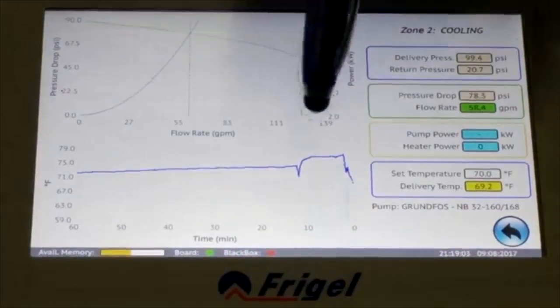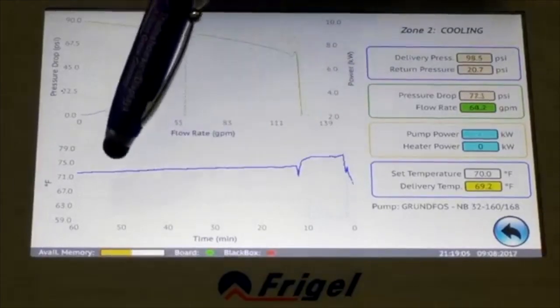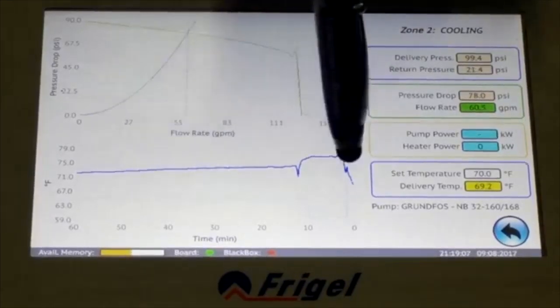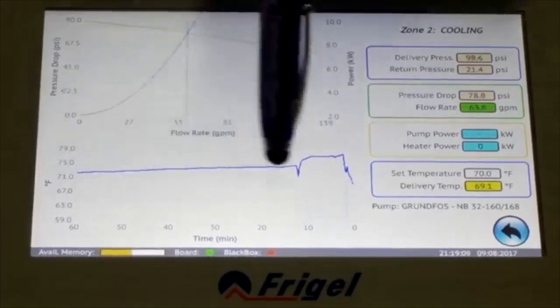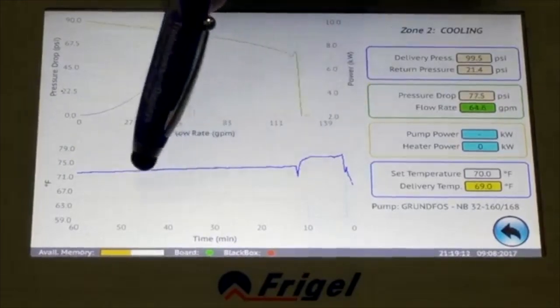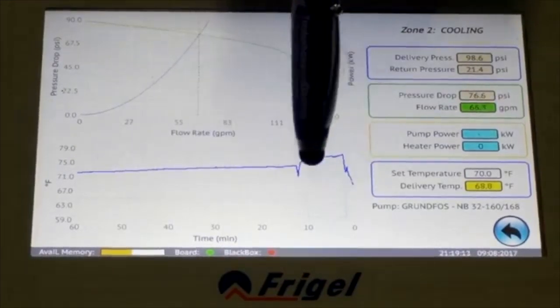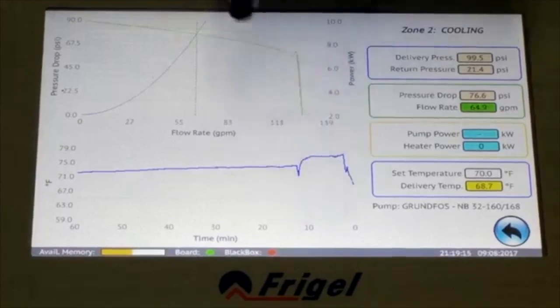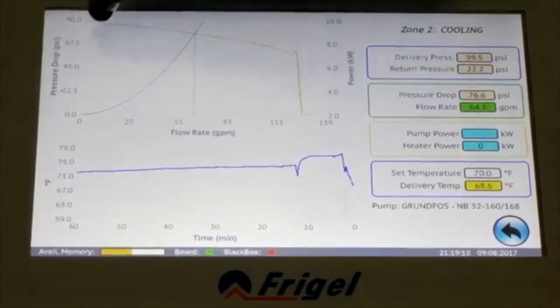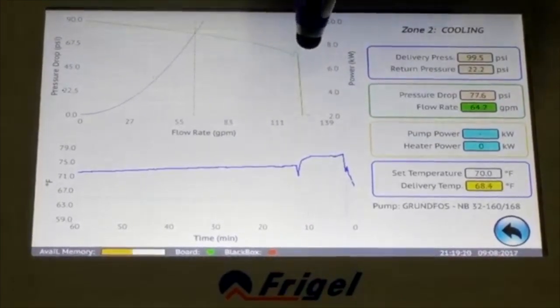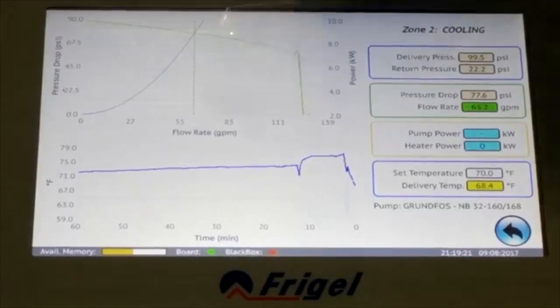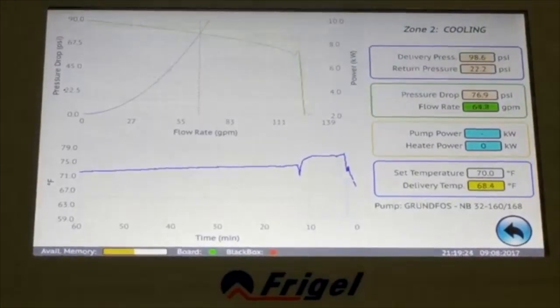In the bottom graph, the temperature and flow rates are displayed over a 60-minute time frame. This can be reset to 0 at any time. In the upper left section, the actual pump curve is shown, indicating flow, pressure drop, and power consumption, also over time. In the right section, pump and heater kW are displayed.